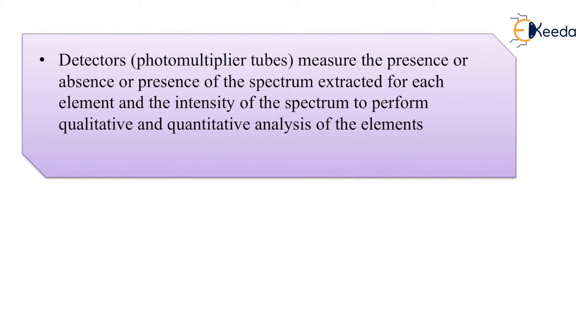Detectors are very important in this process. Here they have taken the example of photomultiplier tubes, though various other kinds of detectors are also available. These detectors measure the presence or absence of the spectrum extracted for each element — once the entire discharge process takes place, the detectors measure the presence of the spectrum of a particular element.